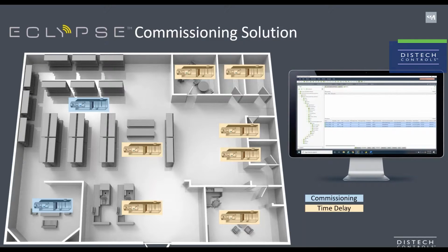Now, how does the ECLYPSE Commissioning Solution initiate and stagger the system test? Let's look at this floor plan. We can assume that these 9 VAVs were selected in the ECNet DC commissioning module. A run all test command is sent to these 9 VAVs. At the same moment, a time delay will be calculated and sent based on the grouping of devices, ensuring that system-level safety trips like high static cutout will not occur during the testing process.